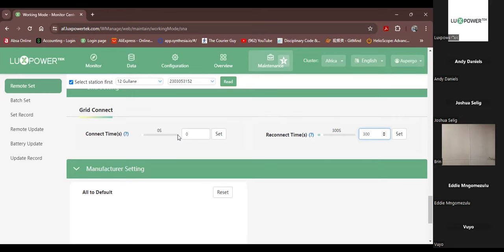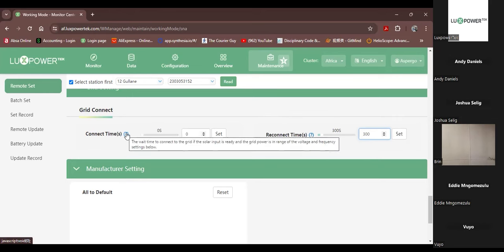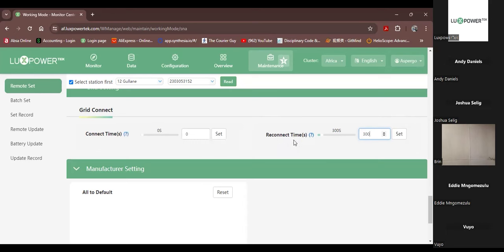This particular one here is for PV. In other words, if you have PV connected and you are exporting PV, then you can also set the wait time to connect to the grid if the solar input is ready and the grid voltage and frequency is within range. But when it says voltage and frequency is within range, it simply means that load shedding is finished. You must also remember that we don't only disconnect to off-grid mode when there's load shedding. We also disconnect and go to off-grid mode when the grid frequency and grid voltage is out of range.